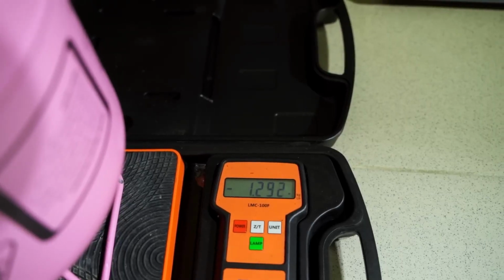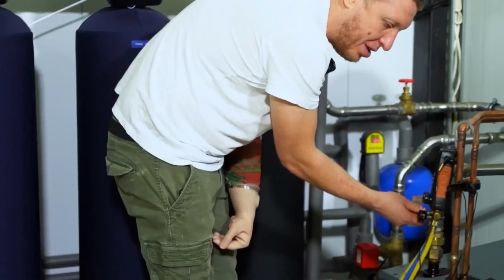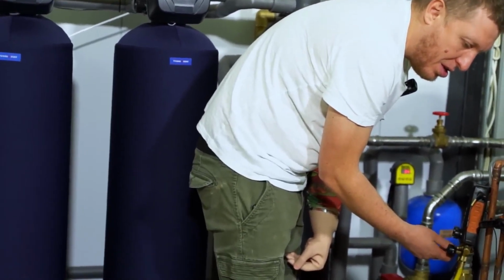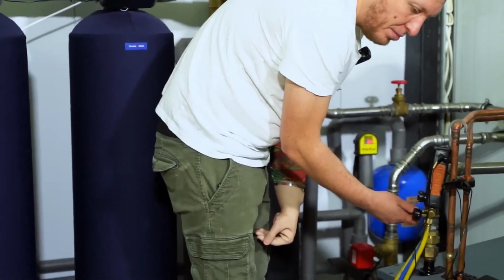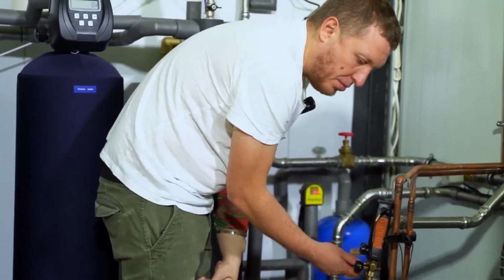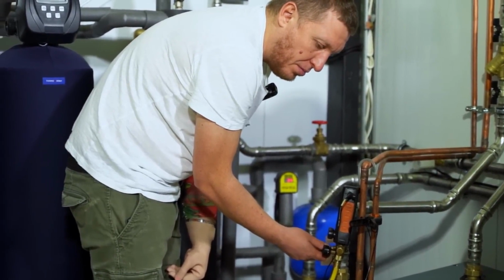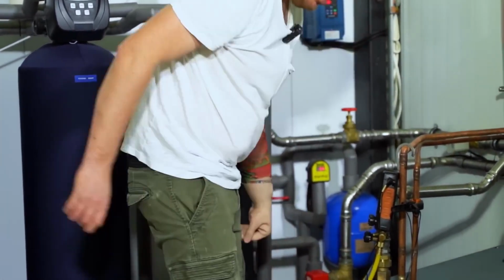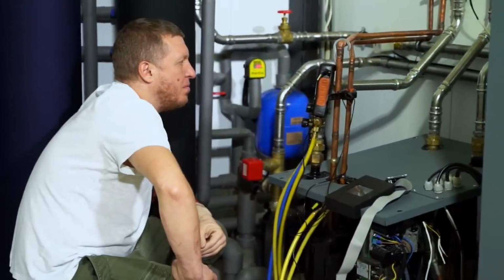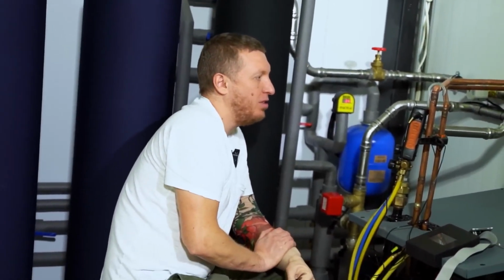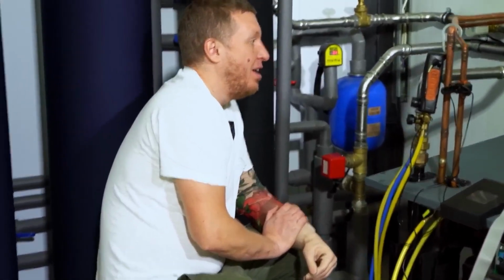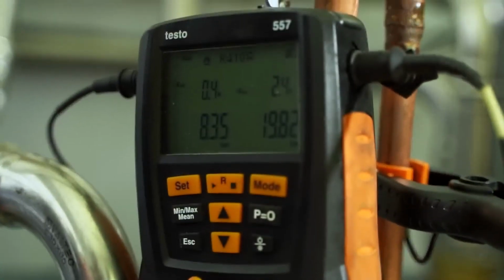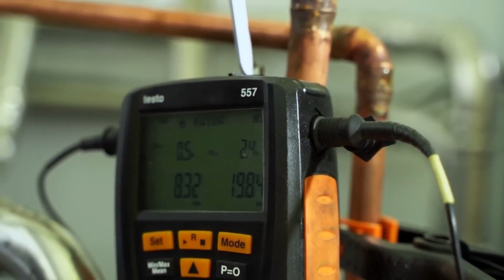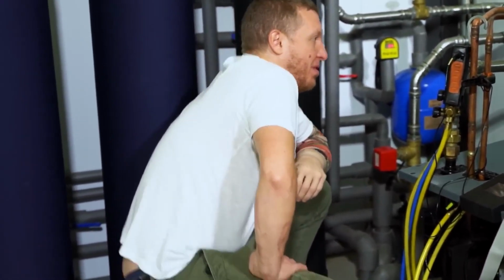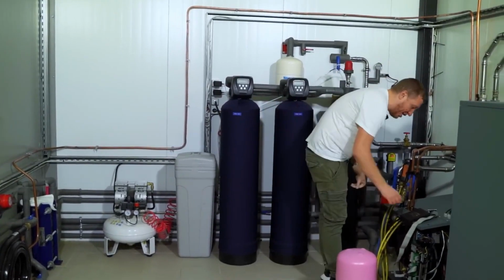Now we'll add another kilogram, turn it up to maximum speed and adjust accordingly. Or better yet, 2. Well, look, gentlemen, now we have subcooling. Here, take a look right here. 2.4 kilograms. Basically, that's fine. That means there's enough refrigerant. This is a subtle point. If you overfill it, the discharge temperature will spike, the compressor will struggle, and things won't work properly. Now let's let it run for a bit and see how the parameters settle. Alright, that's it. Let's crank it up all the way.